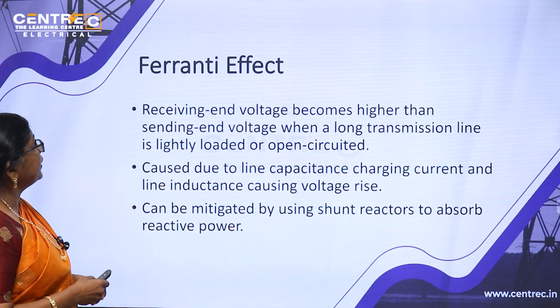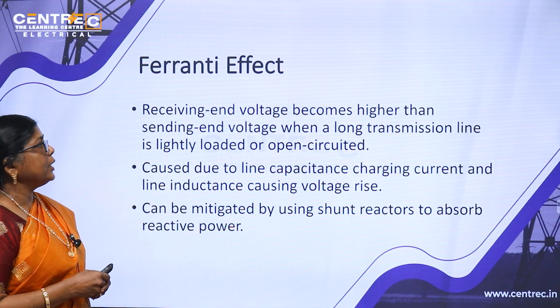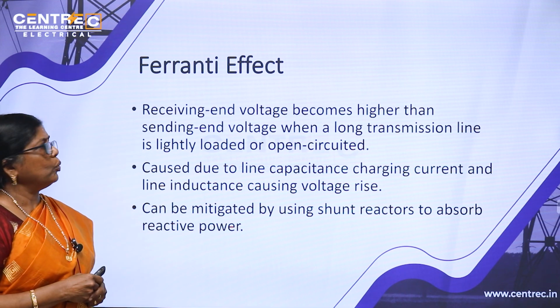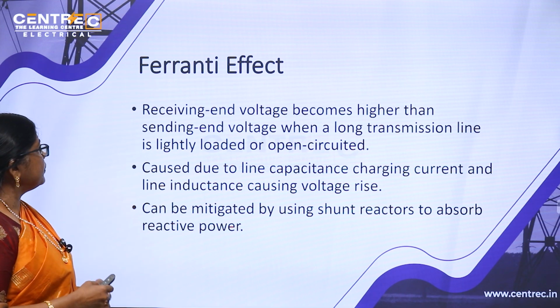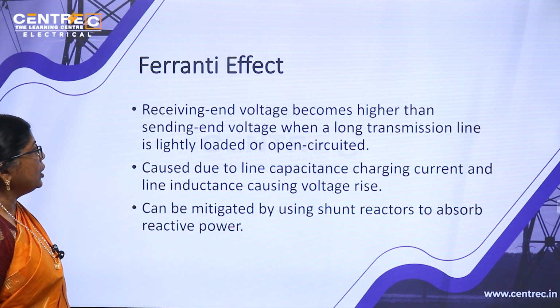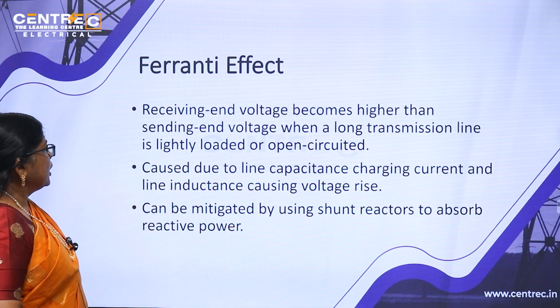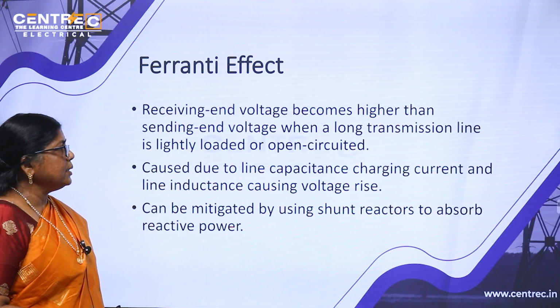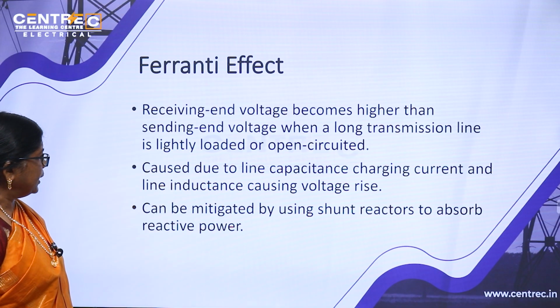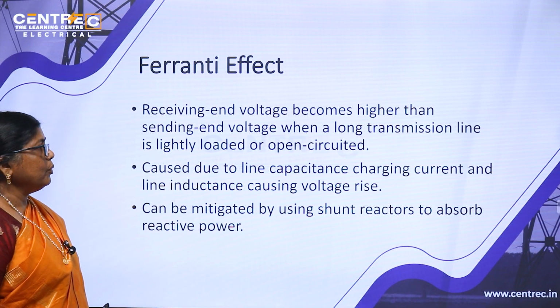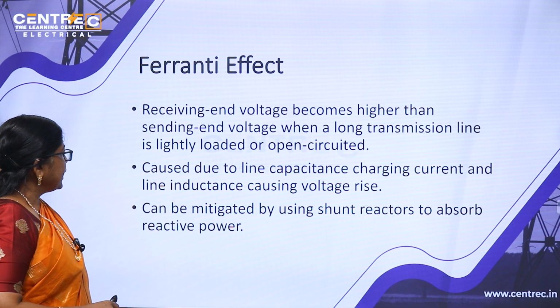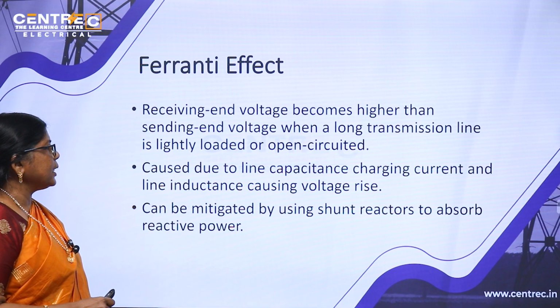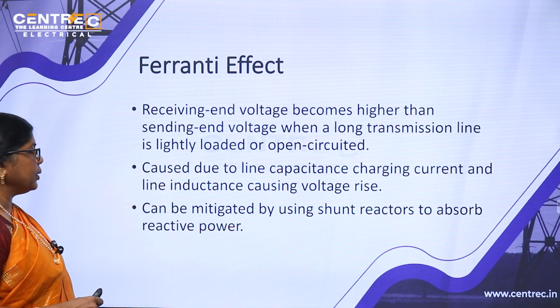Then Ferranti effect: the receiving end voltage becomes higher than the sending end voltage when a long transmission line is lightly loaded or open circuited. It is caused by line capacitance, charging current and line inductance causing voltage rise. It can be mitigated by using shunt reactors to absorb reactive power.